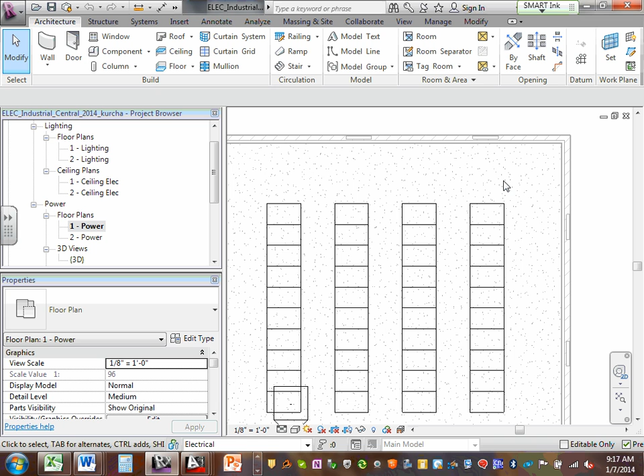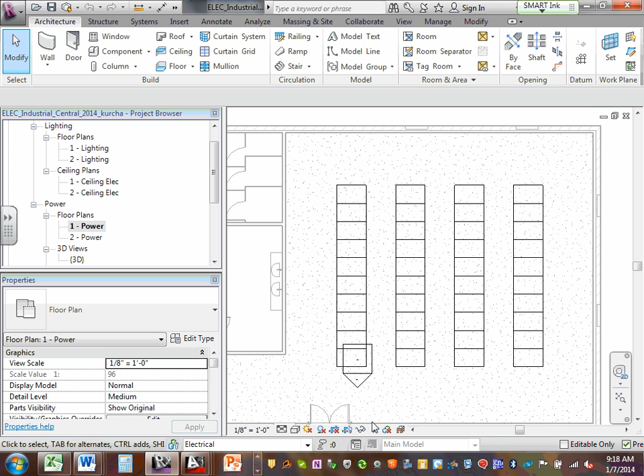So that's kind of the idea of the UPS, and batteries need 5 kW per rack, and I think there's 40 racks that we show. So we'll have to come up with a standard UPS size and a standard PDU size to accommodate that. You're going to be doing a load count this week. You're going to take these 40 squares or rectangles and multiply them by 5K. That will get you the kW size, just for the computers. Yep, and then you'll compare that to standard UPS sizes and standard PDU sizes and figure out where you end up.